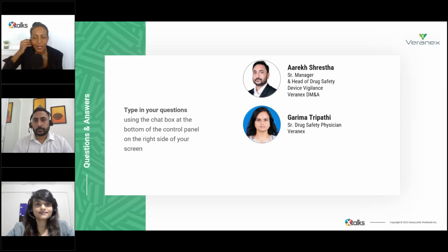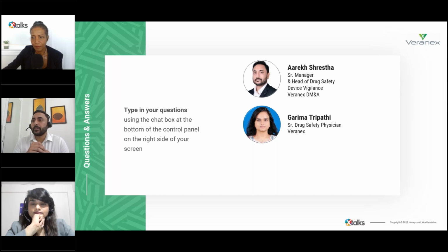This audience member is asking, what are the MDCG, Medical Device Coordination Group, guidelines? I'll take that. Yes. So the Medical Device Coordination Group is recommended by the MDR, Article 103 of the MDR and Article 98 of the IVDR, which suggest that there should be a medical device coordination group. Although the guidelines provided by the MDCG are not legally binding, as I have said earlier, they provide great in-depth insight into the medical device guidelines. They provide a range of documents to assist us in applying the new MDR in accordance with these articles. When we go through the MDR directly, some of the sections, or I would say most of the sections, are not very detailed. So it's open to interpretation.